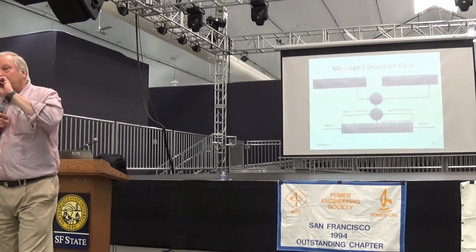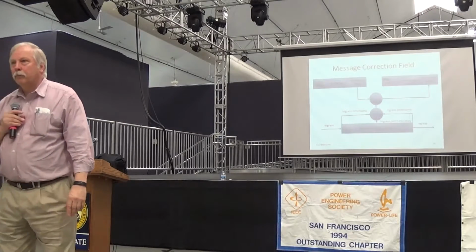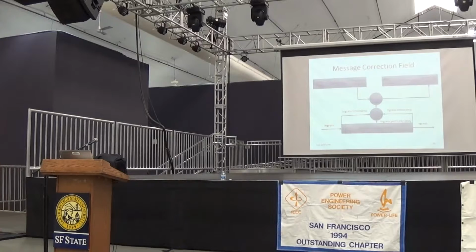The residence time is added to the correction field in the Ethernet message, so that time is accounted for dynamically. Every message that comes into the Ethernet switch has a different residence time that is calculated. So it's completely variable depending upon how busy the Ethernet switch is on any given message. And if there are two switches, each switch is responsible for adding in its residence time.